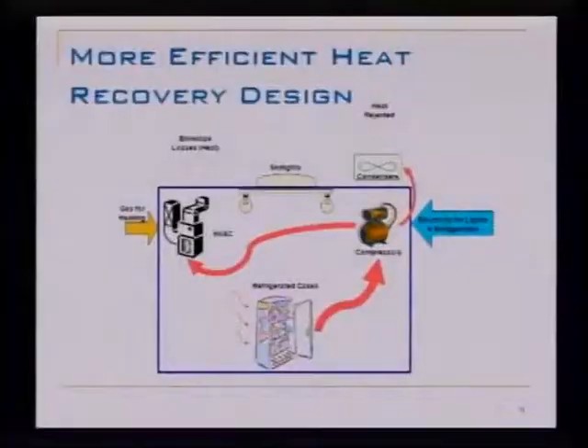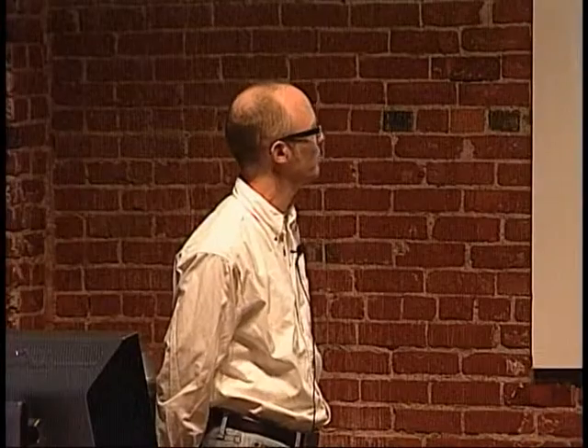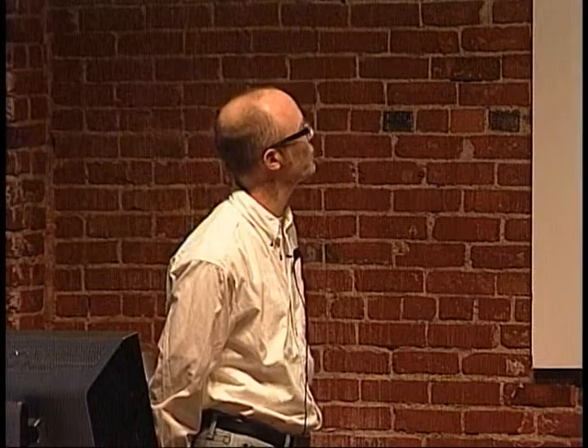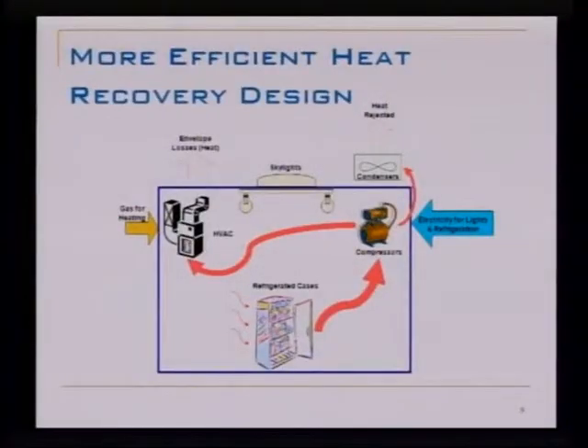Ways to do it better. Add skylights so that we can have less lights. Turn the lights off when the sun is up. Close the doors on the refrigerated cases. Don't have all these open cases sitting on the floor, pouring cold air out onto the floor. And instead of throwing all the heat away on the roof, take that heat and put it back into the air that's going into the store to heat the air back up to keep the people comfortable. So you just try to circulate as much of that heat from the refrigerated cases through the refrigeration system and back into the space. It sounds relatively simple, but to get it to function properly can be pretty challenging.